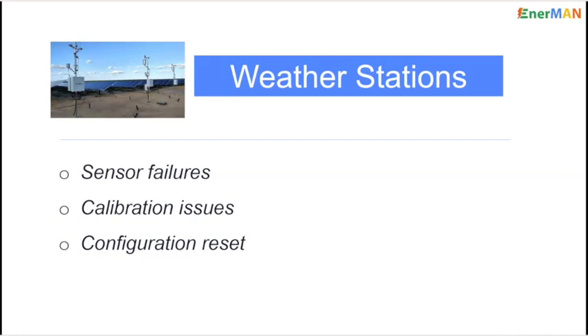There are some settings to be done inside these weather stations, because most of them convert the analog output into a Modbus port, and there are configuration parameters defining sensitivity, gain, and other amplifier-related items. If these parameters are reset, the data coming out of these weather stations is all wrong. And of course, cable damage is a very common issue.